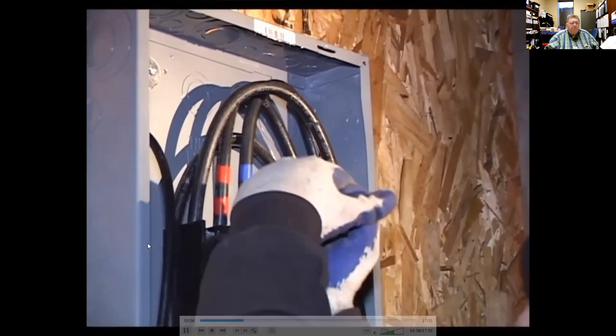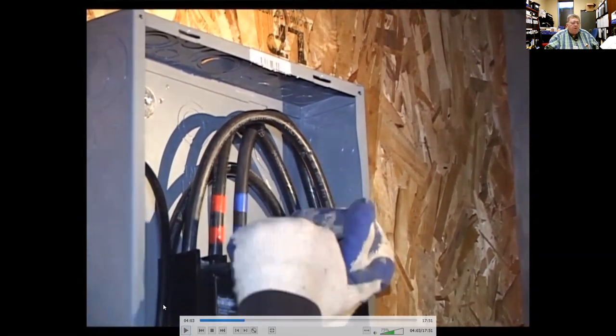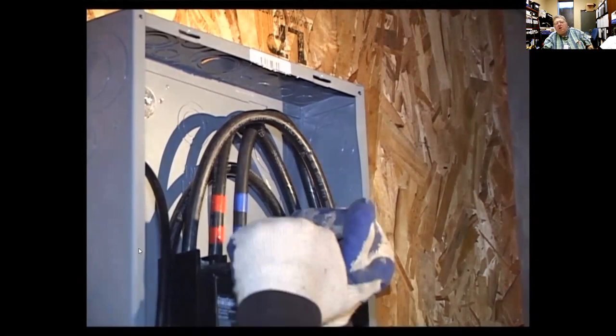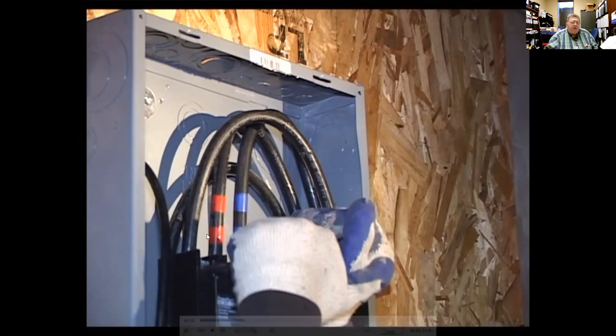When working around exposed house wiring, always assume the wires are hot. Regarding gloves — we use voltage-rated gloves rated for 1,000 volts. They have a rubber part that provides the voltage rating, and then a leather protector glove goes on top. The leather keeps you from snagging or tearing the rubber, which is what actually gives you the electrical insulation. The leather portion just protects the rubber from cuts and contamination. This video has some age on it but the main content is fine.